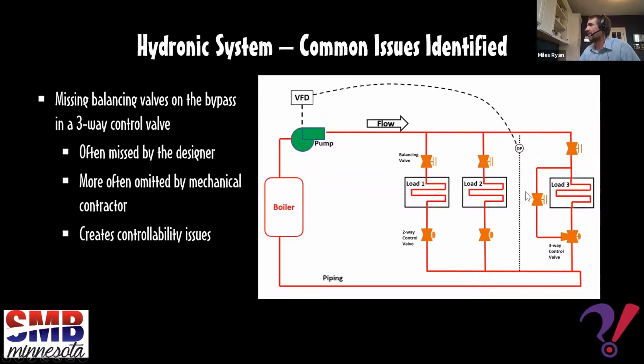And because it dropped there, the pumps responded just the opposite of what we'd expect them to do. They sped up. The lead pump told the lag pump to turn on as well. Then they both sped up together. And then they got to 60 hertz and they stayed there for 4 months. And the frustrating thing is we brought this to the team, and there were probably 4 meetings between the owner, the design firm, us, the commissioning providers, and the contractor, trying to talk him into why this was needed. And at the end of the day, the design called for it. It was needed. They did install it, and I was there. They installed it, we balanced it, and that system has been running just fine ever since.